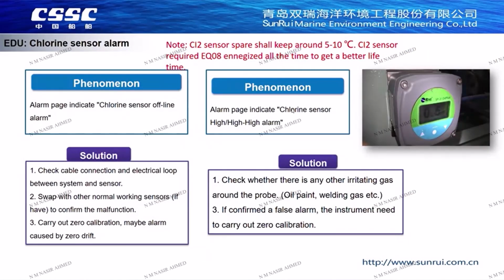The next one is the chlorine sensor alarm. It should be noted that the chlorine sensor requires constant power on. Spare parts for storage need to be stored in an area at 5 to 10 degrees to prevent chemical volatilization in the sensor probe and loss of detection activity. Similarly, zero drift easily occurs within about 30 minutes of power on. When an alarm occurs, the wiring needs to be checked. Also, zero drift shall be considered.